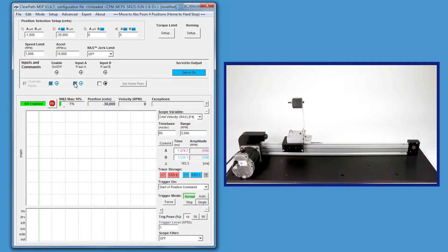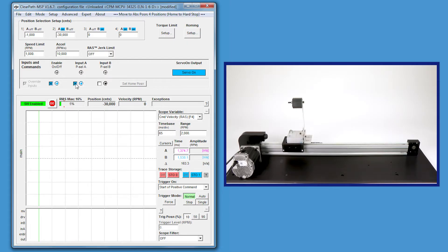This creates a jerk-limited and jerk-derivative-limited motion profile. So instead of having an abrupt change when going from a standstill to an instantaneous acceleration rate, the RAS rounds this transition point by creating a gradually increasing acceleration rate up to the acceleration limit. These points of inflection in a motion profile get rounded out, creating a much more mechanically friendly profile, meaning the mechanics are being asked to gradually ramp up to a given acceleration rate and gradually slow down to a specific velocity or zero velocity.